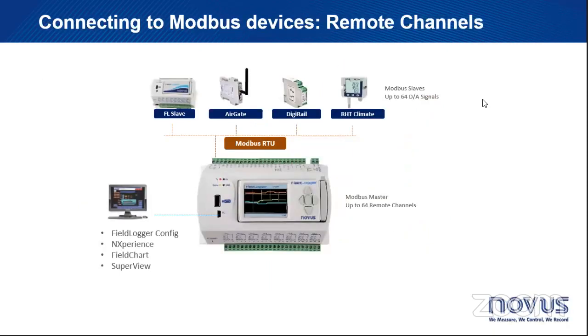Also, one possibility would be connecting to Modbus devices. So I have received several cases where I have a FieldLogger, okay? And my customers want to read temperature and humidity, for example. And they will wire 4 to 20 milliamps input transmitters to its analog inputs. But in other cases, why don't you go for Modbus RTU transmitters directly? That comes with the flow meter as well. We know the FieldLogger has all the features that will allow you to read a pulse input. But in some cases, it's just easier to connect an RS-485 flow meter to it, okay?